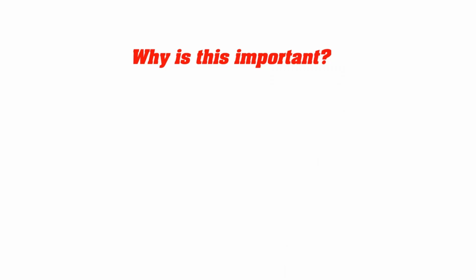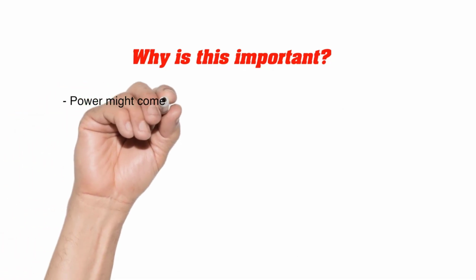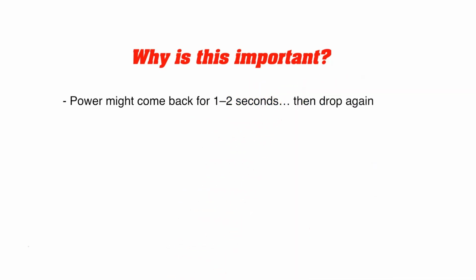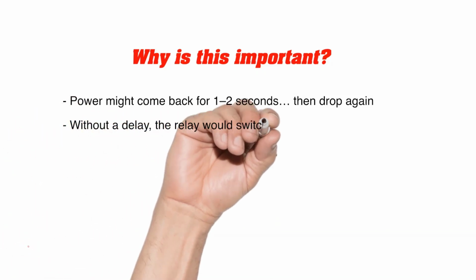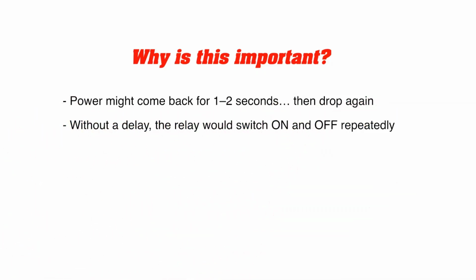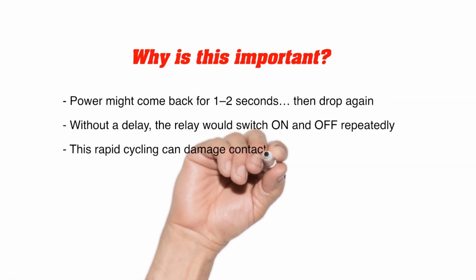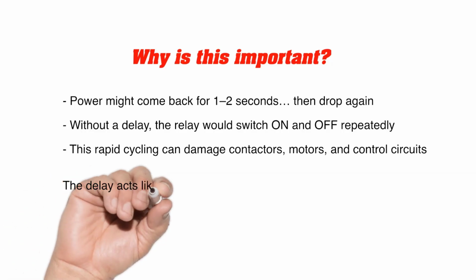Why is this important? Because in real electrical systems, faults are often unstable. For example, power might come back for 1 to 2 seconds, then drop again. Without a delay, the relay would switch on and off repeatedly. This rapid cycling can damage contactors, motors, and control circuits. The delay acts like a stabilization period. It ensures the power supply is truly stable. The system avoids unnecessary stress and equipment restarts safely.